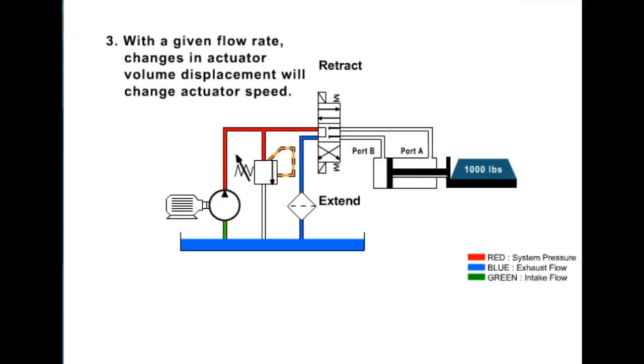Principle 3: With a given flow rate, changes in actuator volume displacement will change actuator speed. With less volume to displace, the actuator will cycle faster. For example, there is less volume to displace when we retract because the cylinder rod occupies space, diminishing the volume to be displaced. Notice the difference in speed between extend and retract.